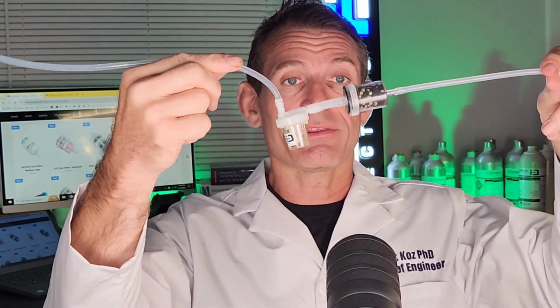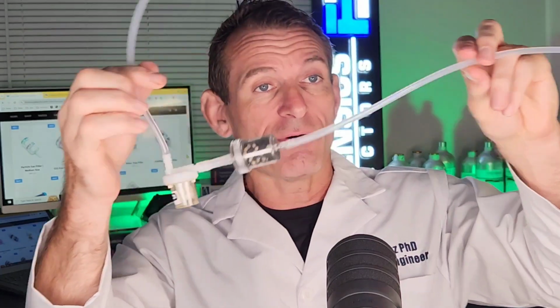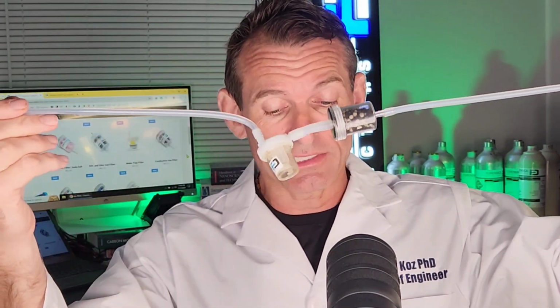Now, for different applications, we need different filters, but what's common amongst all of them is that they're inline. See, they are inline. In other words, you have on one end your probe, on the other end is the analyzer. I'll explain how that works right now, so there's totally zero confusion. Typically, when we're doing gas analysis, we have some type of probe. It could be our pistol probe, it could be our 6-inch probe, it could be our 3-inch probe, it could be a different probe, but there is an intake.